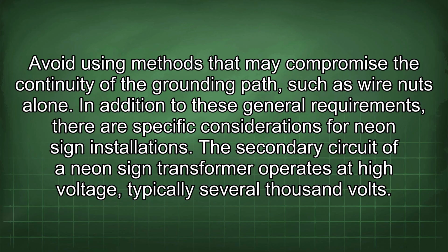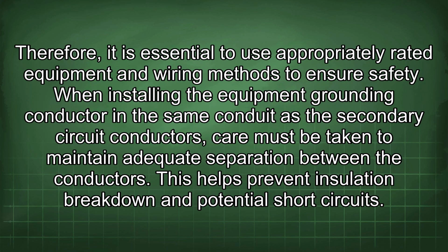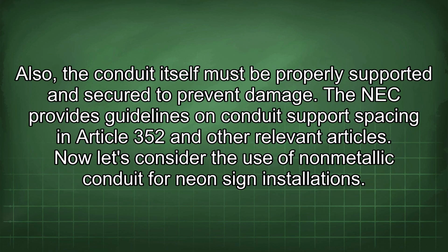In addition to these general requirements, there are specific considerations for neon sign installations. The secondary circuit of a neon sign transformer operates at high voltage, typically several thousand volts. Therefore, it is essential to use appropriately rated equipment and wiring methods to ensure safety. When installing the equipment grounding conductor in the same conduit as the secondary circuit conductors, care must be taken to maintain adequate separation between the conductors. This helps prevent insulation breakdown and potential short circuits. Also, the conduit itself must be properly supported and secured to prevent damage. The NEC provides guidelines on conduit support spacing in Article 352 and other relevant articles.